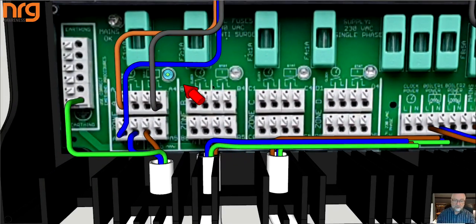The LED on the board gives information along with the LEDs on the OpenTherm system. If that LED is ever lighting, you know that power has left fuse one and has arrived at terminal one and has arrived at terminal four. So this is telling you the pump should be running in that scenario, or if it's a valve, the valve should have power, and also that the boiler should now be calling if the boiler is wired onto the board directly, if it's not using OpenTherm.